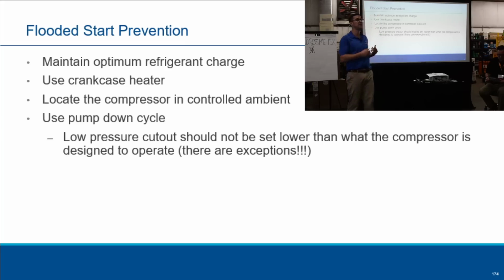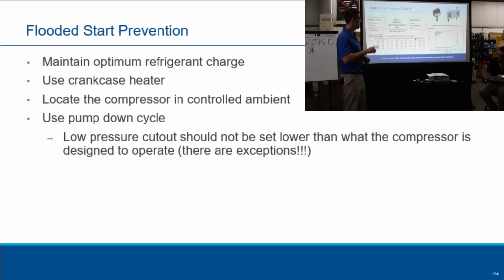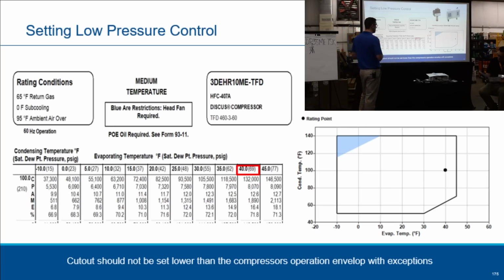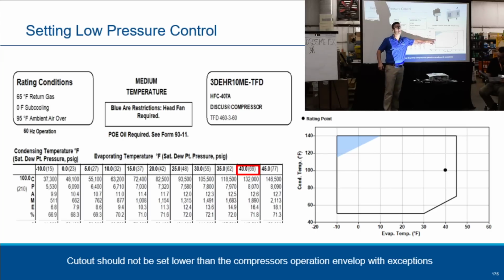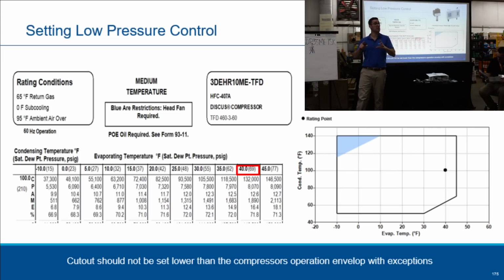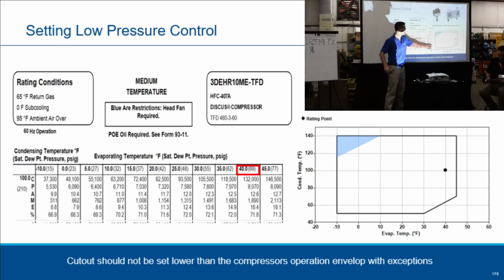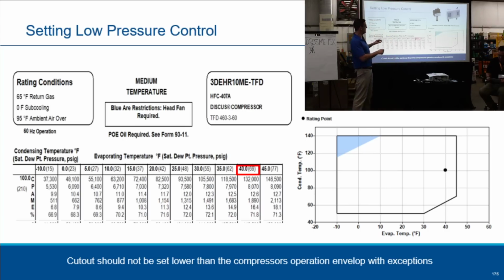Well, I was told set it to 2 to 5 psi. When it gets down, it cuts out. Right? Medium temp, 15 psi. Okay? But what the problem is with that is this is an operation envelope right here. Does everyone see this on the right side? Okay, that's an operation envelope. Copeland makes an operation envelope for every compressor. So we can help you guys know when you're running outside, as well as the OEMs to design these compressors. So now, for an example, I'm using our product selection software here.